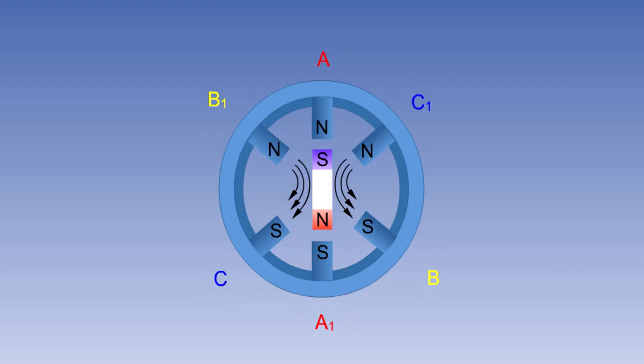If a bar magnet is suspended in a rotating magnetic field, it will lock into the field with its south pole staying with the rotating north pole, and its north pole staying with the rotating south. The magnet will therefore rotate synchronously with the field, at the same speed as it. This is the principle of operation of the synchronous motor.